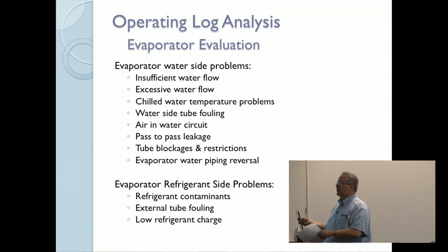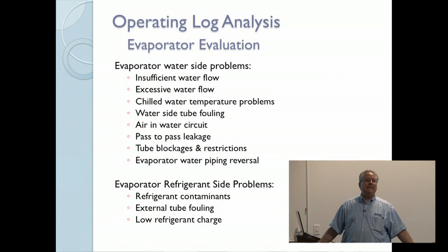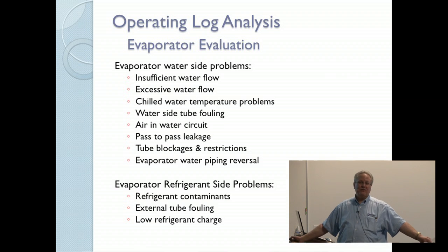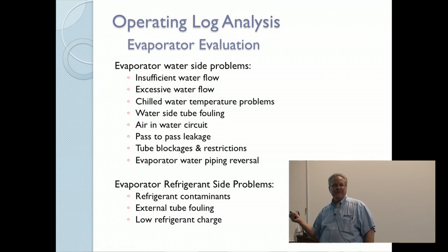So I remember we were having problems with one chiller. We ended up, in addition to oil analysis, paying quite a bit more to get a refrigerant analysis done. We found they had 16% oil in this machine when they should have had at most a couple. It cost them a fortune on efficiency.